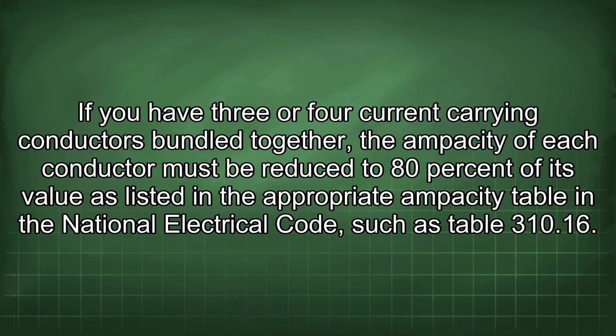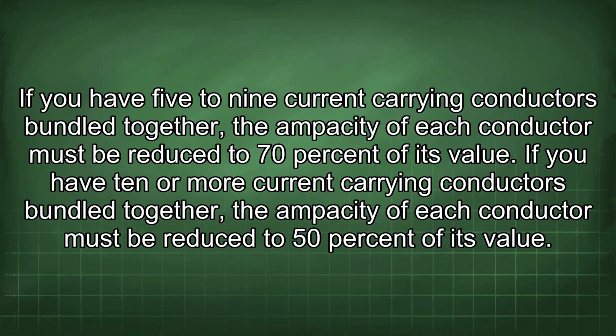If you have 3 or 4 current-carrying conductors bundled together, the ampacity of each conductor must be reduced to 80% of its value as listed in the appropriate ampacity table in the National Electrical Code, such as Table 310.16. If you have 5 to 9 current-carrying conductors bundled together, the ampacity of each conductor must be reduced to 70% of its value. If you have 10 or more current-carrying conductors bundled together, the ampacity of each conductor must be reduced to 50% of its value.